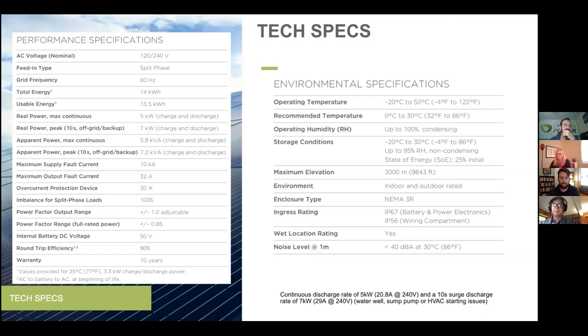I'm sorry, Oliver. If I'm understanding the question correctly, we don't want to install more than about a 7 to 8 kilowatt system per Powerwall. Oliver, I'm not familiar with your system. I don't know if you have SolarEdge or Enphase as your inverters, but essentially, we don't want to put more than about 25 panels on one Powerwall. If you had, for example, a 40 panel system with only a single Powerwall, we would split things up so that only 25 of those panels are charging that Powerwall. Everything else would be tied into your regular home the way that it normally would, sending that power back to the grid in the event of overproduction.